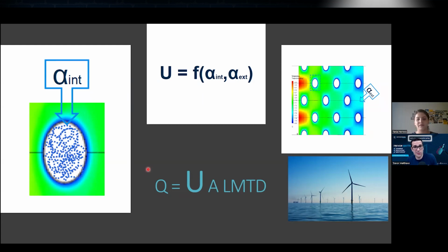But you need it. I've seen so many on the coast where it's just the tubes. There's nothing left because it just corroded all the fins off, and it's just the tubes pretty much left. So it's important to have that in certain areas, those corrosive areas. So that's great to know.